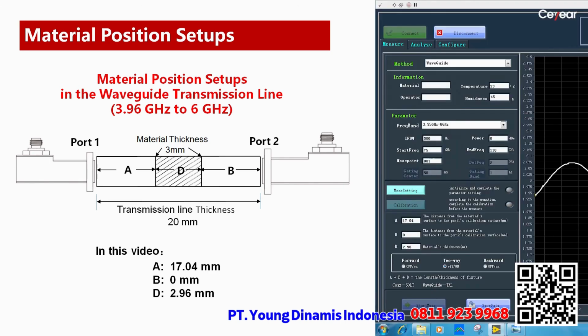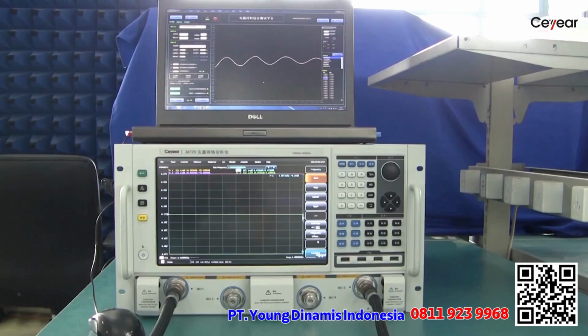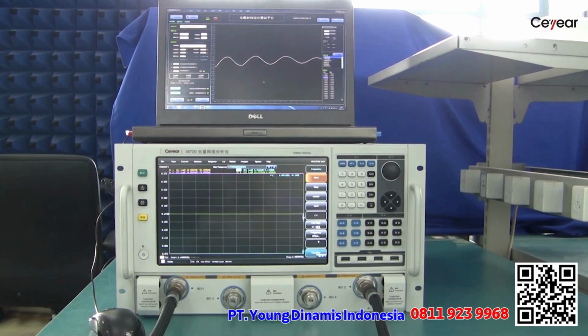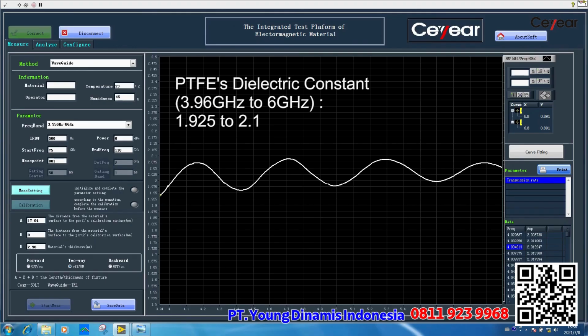So we input the values A, 17.04 mm, B, 0, and D, 2.96 mm into the panel, and press the Start Measure button. We can see from the screen that the dielectric constant is about 2.0 from 4 GHz to 6 GHz. It is a widely accepted value for PTFE.